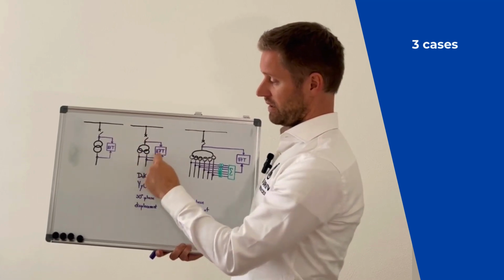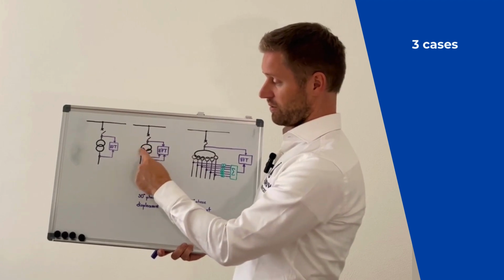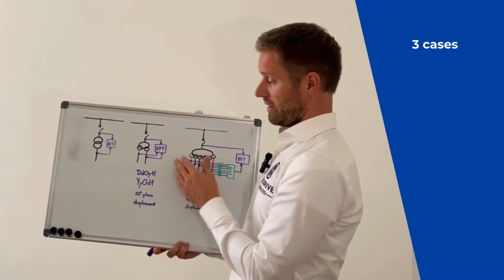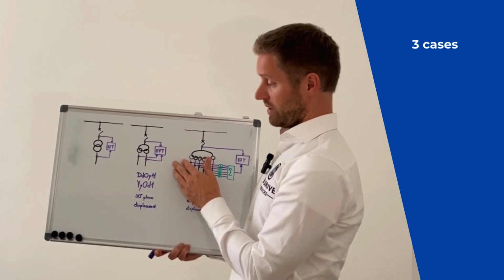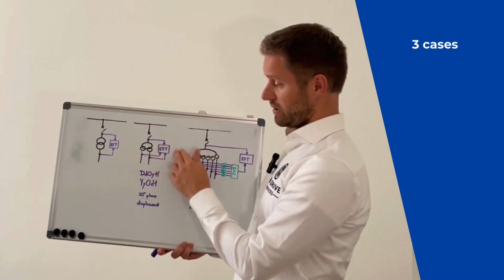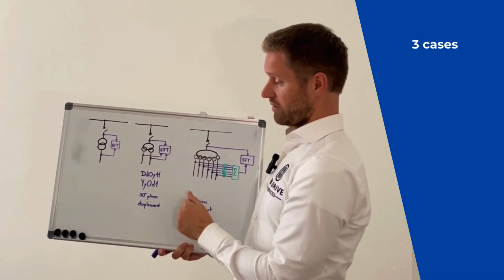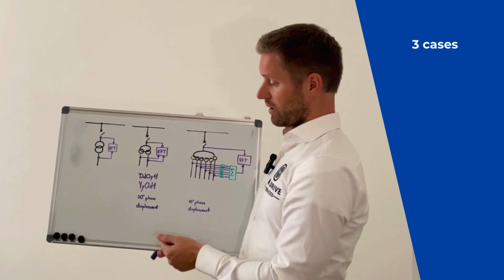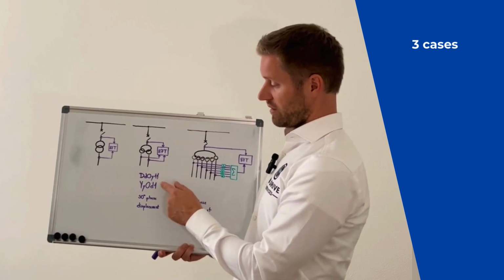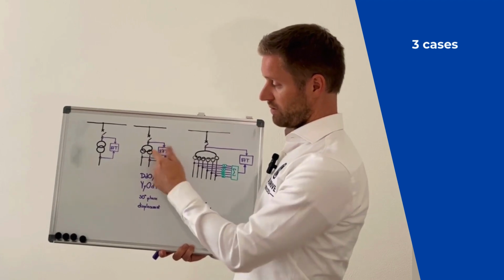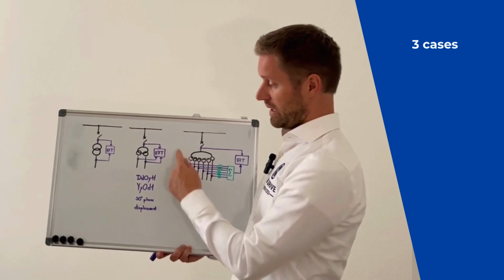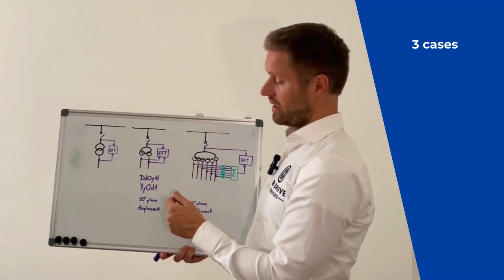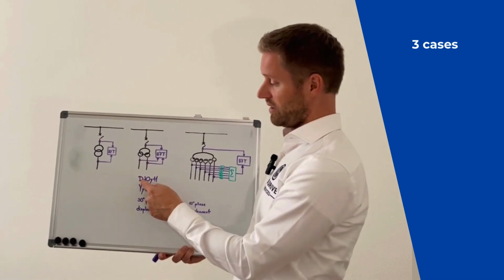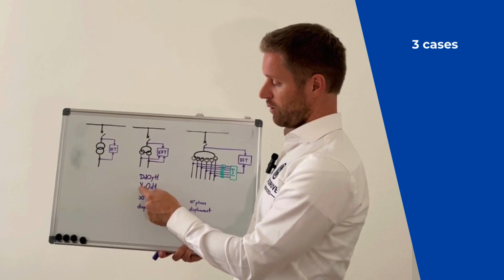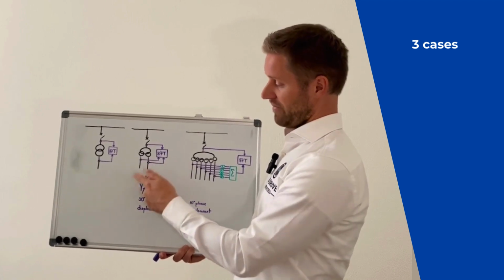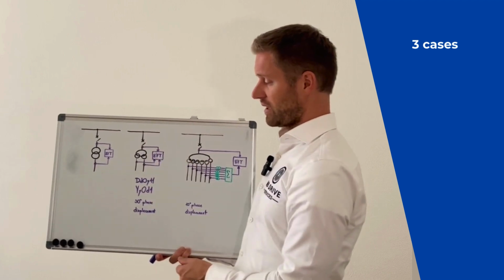If we have a transformer like here, a three-winding transformer with two secondary windings, then the implementation is still quite simple. It's because most of the modern differential protection relays would support such a configuration, meaning you could select the winding connection or vector group of the specific transformer in the relay software itself. So it could be, for example, D0, Y11 or Y0, D11 as examples of a three-winding transformer.